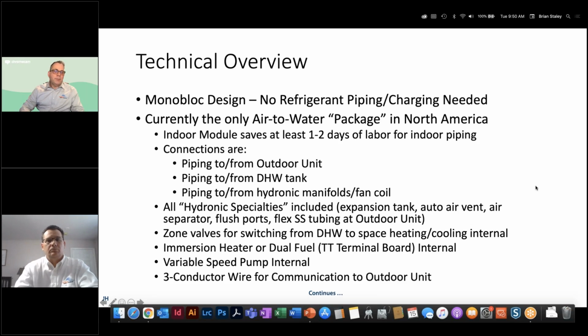If we're looking at backup, we have a choice of either an immersion electric heater for all electric systems, or if we have a boiler backup, we can go with a dual fuel module. And in that case, now we're going to energize the boiler instead of that electric heater.